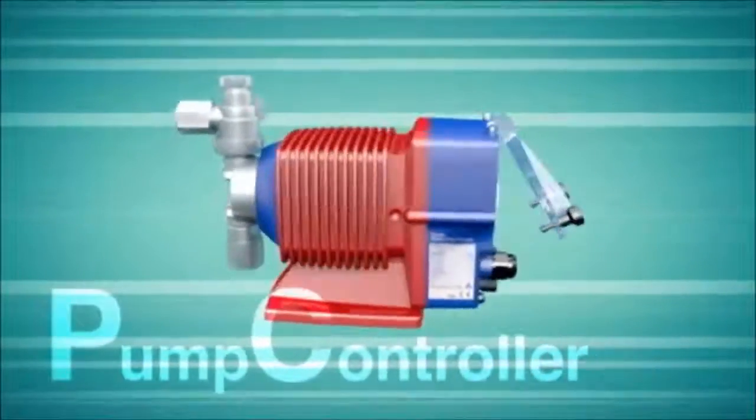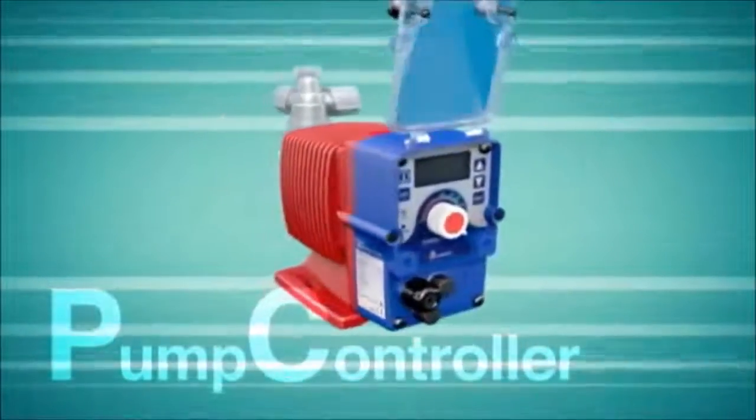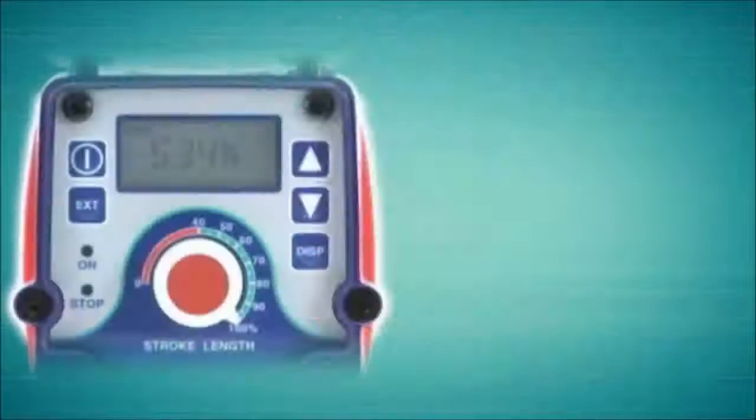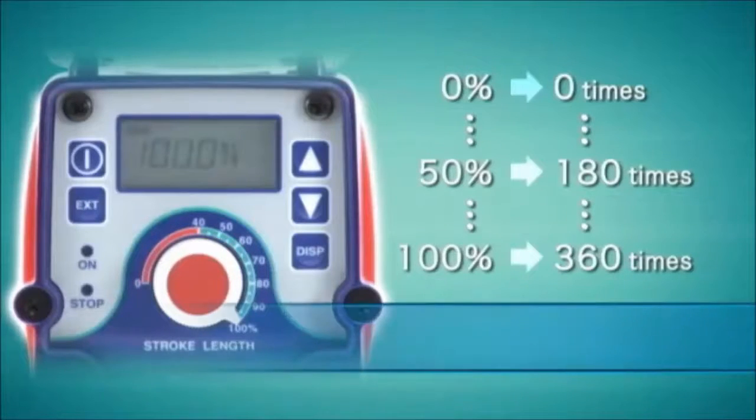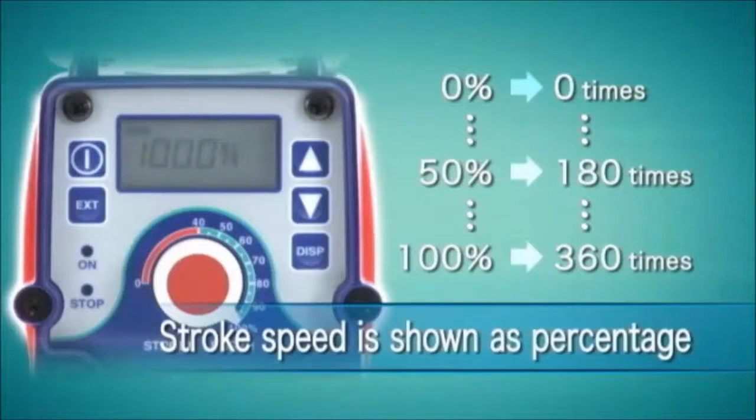The pump controller utilizes several control methods for output control. Manual control is achieved through stroke length adjustment or pump speed adjustment, or a combination of both. Stroke rate is displayed as a percentage of full speed or one of several flow rate units.